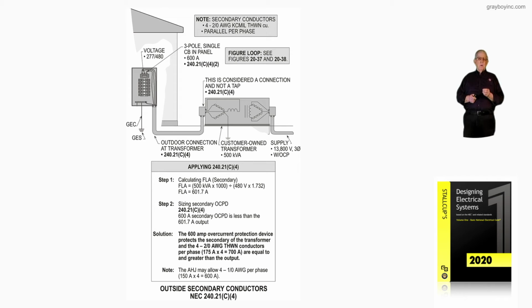Now notice we have a 600 amp overcurrent device in step 2 that's in the illustration. So we are protecting that transformer output in step 2. Now the solution is, from the secondary side of that transformer, we terminate in a 600 amp device with 4 2-aught conductors parallel per phase. A 2-aught conductor, if we reference table 310.16, has an ampacity of 175 amps from the 75-degree column. 4 of them in parallel is 700 amps. So our overcurrent device is protecting the conductors, the output of the transformer, and the panel board at 600 amps.